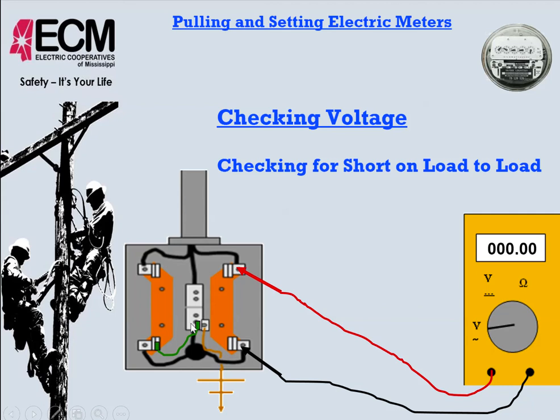So by grounding one of them, we've already established that they're not hot. Then we could ground one of them. If we grounded this one, this one also would be grounded. And if we check here with the voltmeter on voltage, it would read 120 volts if they're tied together. If they're not tied together, it will read 0 volts, and that's what we're looking for.